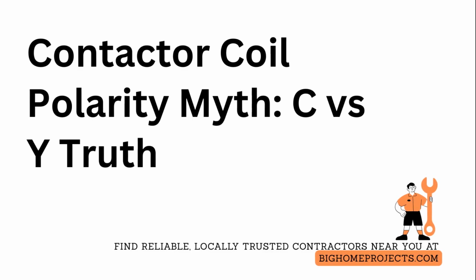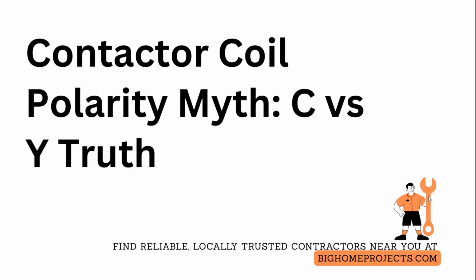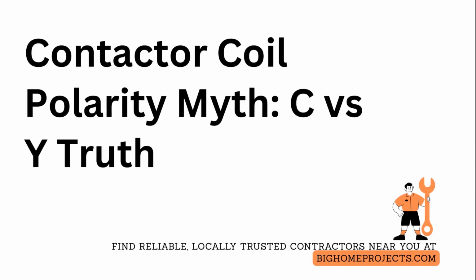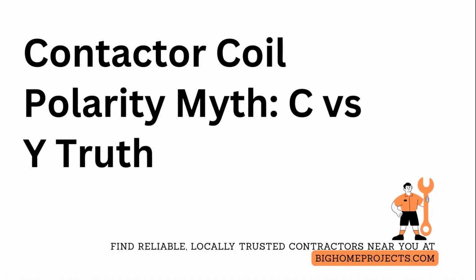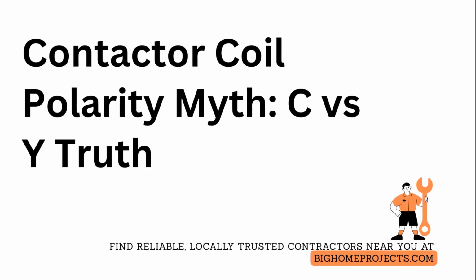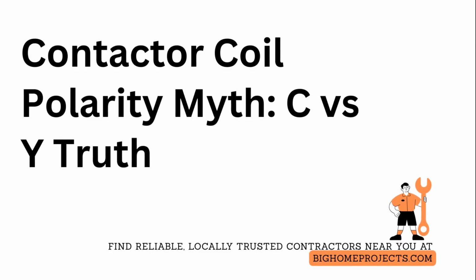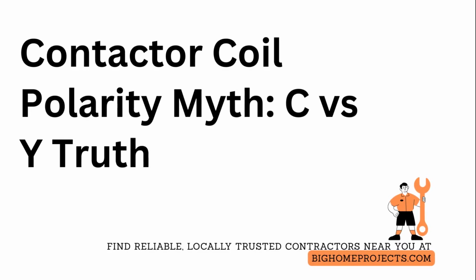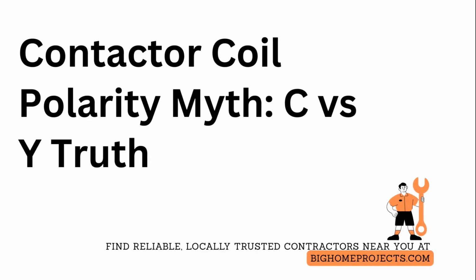Wire the condensing unit control coil to the common and the switched hot from the thermostat. Polarity does not affect the coil, so you can safely use either the C or Y conductor as long as one is the actual common return and the other is the switched call for cooling.